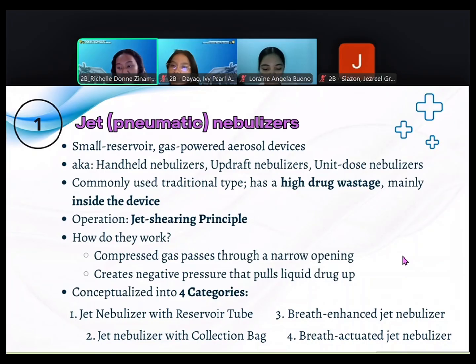In the jet shearing principle, compressed gas is forced through a narrow orifice at high velocity, creating a low pressure area. We are familiar with this, which is the Venturi effect, which then draws liquid medication up the capillary tube. This fast gas stream shears the liquid into droplets, and the larger particles are impacted by baffles and are returned to the reservoir, while smaller respirable particles are carried toward the patient. So, as I said, how do they work? Again, compressed gas passes through a narrow opening. It creates a negative pressure that pulls liquid drug up toward the patient.